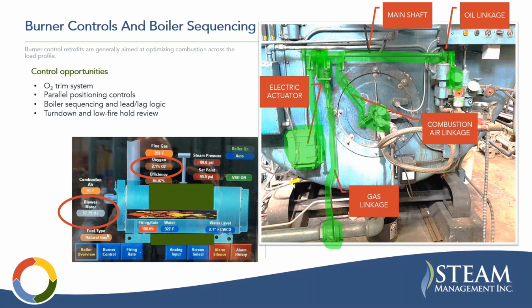At a minimum, modern burners and boilers are going to have parallel positioning, which is at least independent actuation of fuel and air, and maybe that's just run off a control curve and not actually reading O2. And then some other control upgrades are improvement of boiler sequencing and lead lag logic. And also you could conduct a turndown and low-fire hold review to evaluate cycling issues.